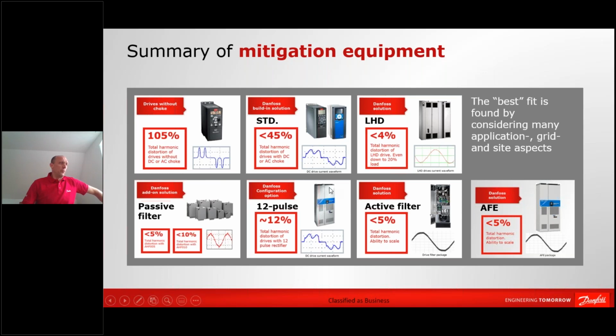So the first two standards that you see up in the left hand corner have, for instance, a micro drive without a DC choke. You can see the current distortion here is 105% total distortion. And these are actually the drives talked about earlier, below 7.5 kilowatt, where you have a relatively high distortion level. And you should use them only in situations where you have very little loading on your transformer, simply because you will end up generating a lot of noise when you have hundreds of these in your installation. So be cautious with drives without DC chokes in general.